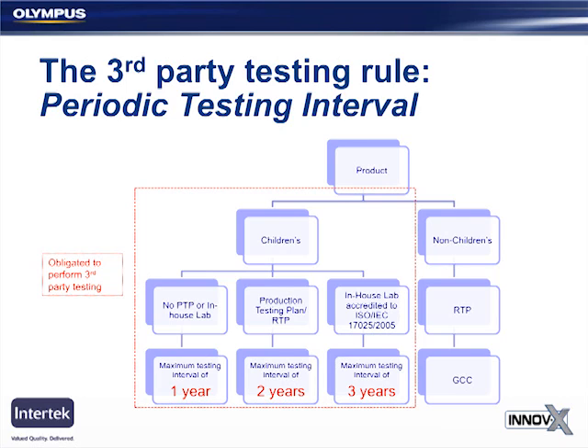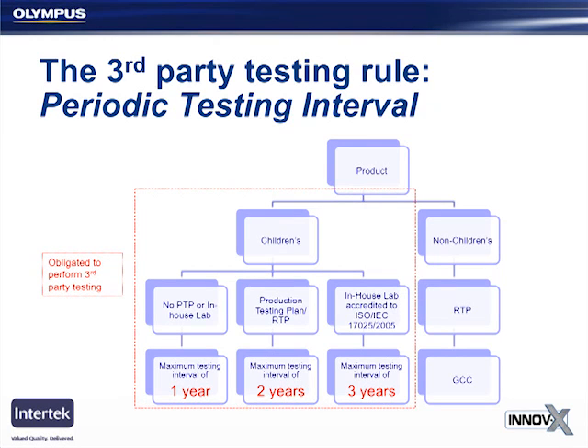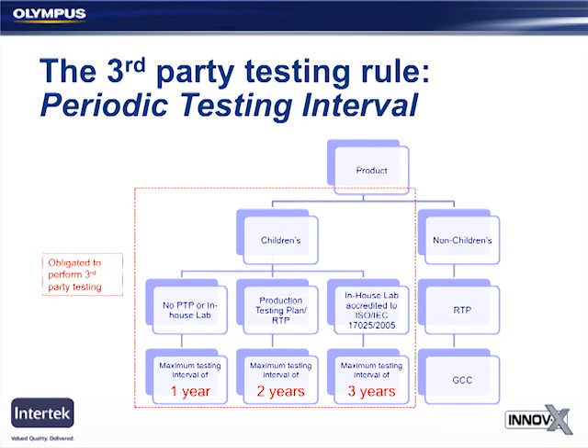If you have no other periodic testing in place, which means you are only controlling your risks by sending the samples to the lab, the maximum testing interval is up to 1 year, while it is 2 years if you have a production testing plan or reasonable testing plan in place, and a maximum of every 3 years if you have an in-house ISO or IEC accredited lab. Of course, a number of factors listed in the regulation will have an impact on your final decision.